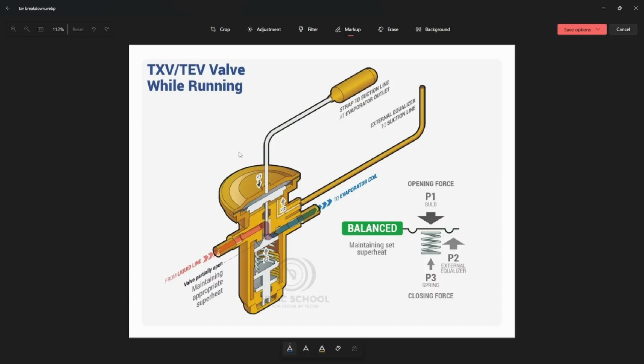So we've got our power head, which is this top part right here. The power head is what does all the work. We talked about that already. We've got three different forces. We have our bulb force, which is the opening force. That's what actually puts pressure on our diaphragm right here, which pushes down on our needle to actually open or close this orifice area to restrict or open up to allow more refrigerant through. That's our first force. That's our opening force.